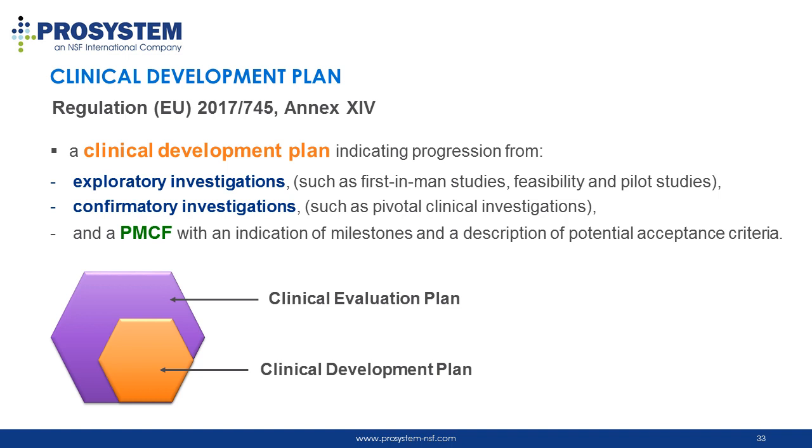A clinical development plan should indicate the progression from exploratory investigations, such as first-in-man studies, feasibility and pilot studies, to confirmatory investigations, such as pivotal clinical investigations and planned PMCF activities, with the indication of milestones and potential acceptance criteria.